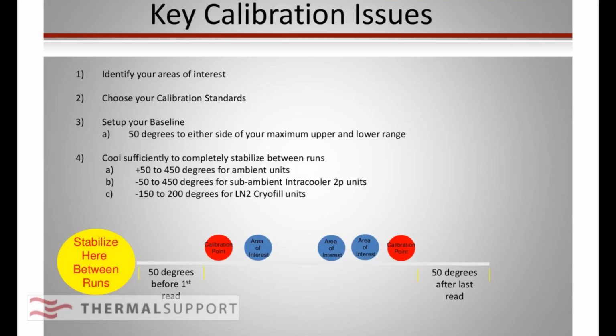Because you don't have metals that go down there. You've got your standard indium, tin, lead, and zinc. And then if you want to get down in the lower area around room temperature, you've got gallium. You want to go down around -30, you've got mercury. A lot of people don't like to use mercury. It makes some great calibration material.